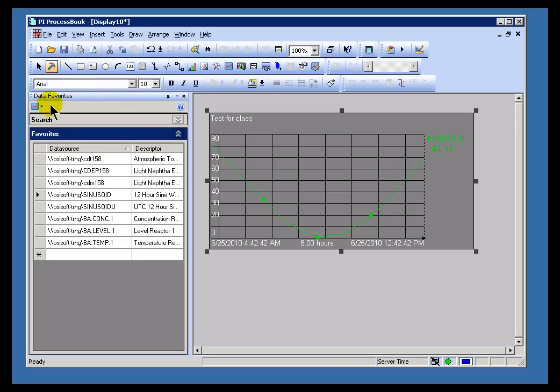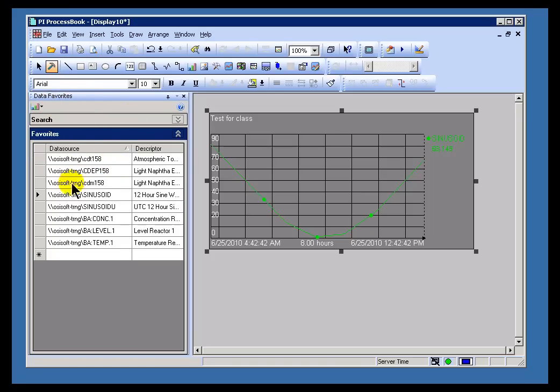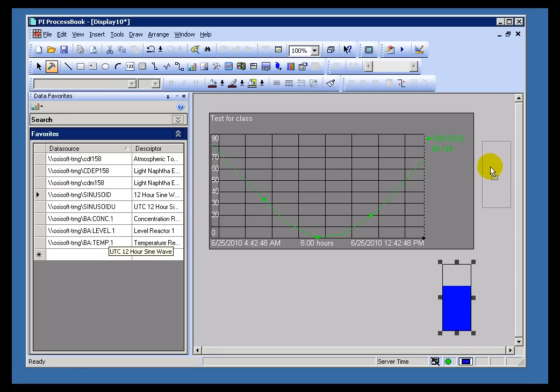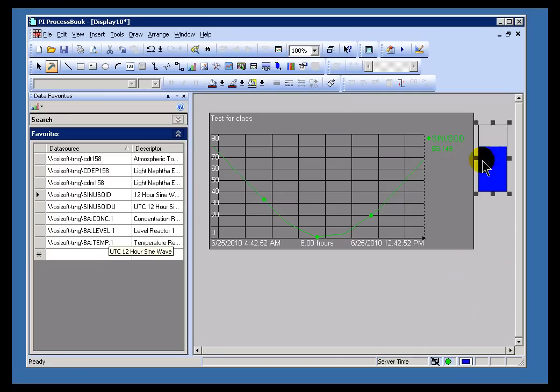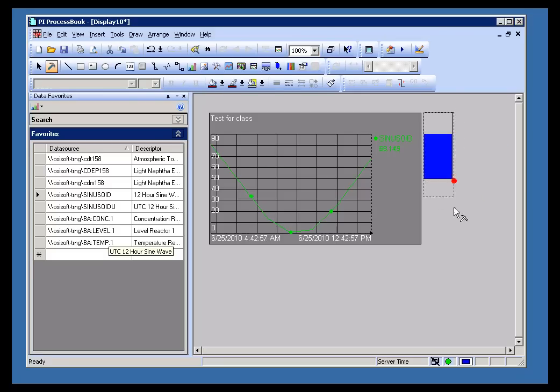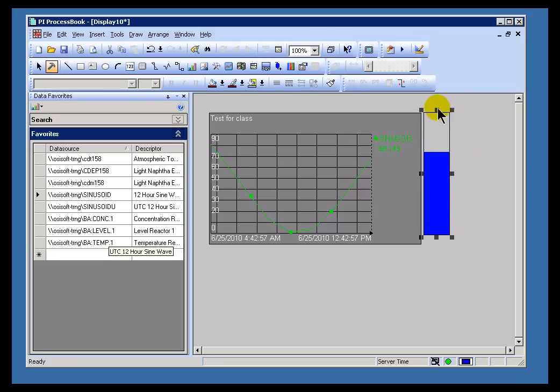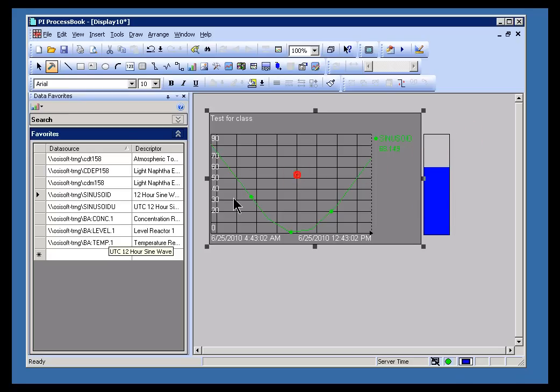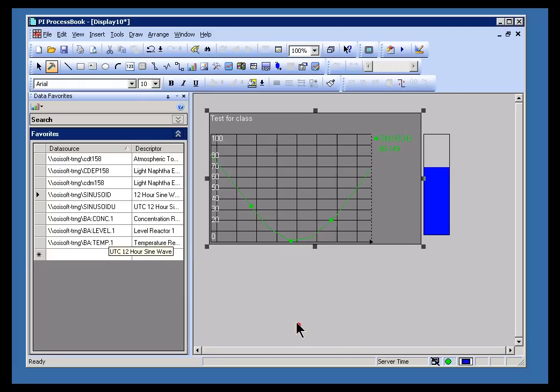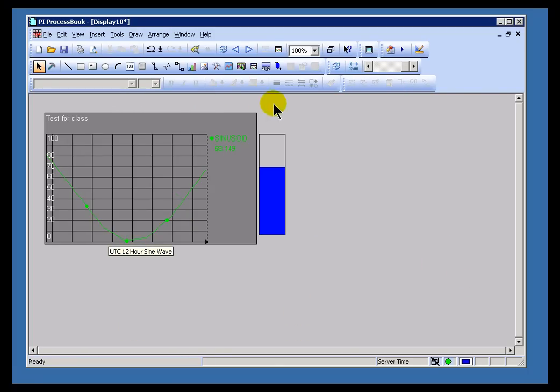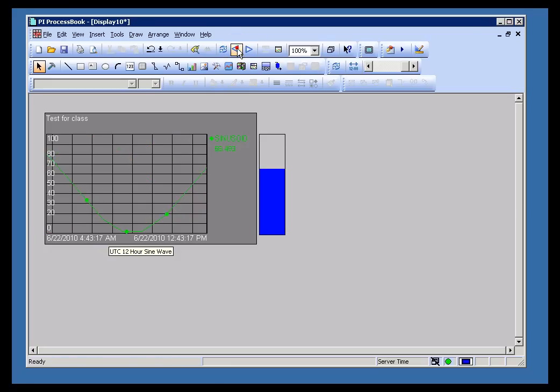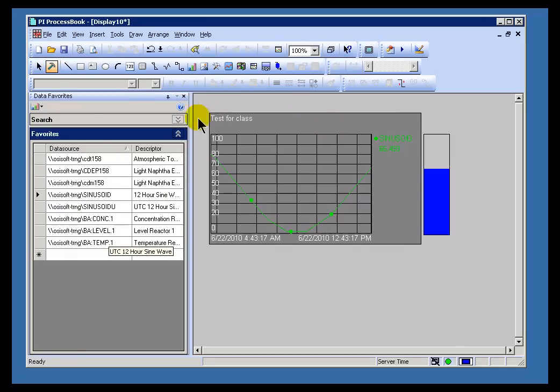The second thing I can do, let me add a Bar Graph. So I'll switch over to Bar. Same thing, Sinusoid, drag that over here, and then format it the way I want. I think I'll put that right about here. So it's going to track. Let's have it track exactly what the Trend is doing. Let's make it the zero and span match what we see in the Trend. And to do that, I'm going to change this to, instead of Auto Range, let's change this to Database. So what we should see now as we scroll backward and forward is that value and the Trend value should always parallel each other, and that's what we're seeing here.